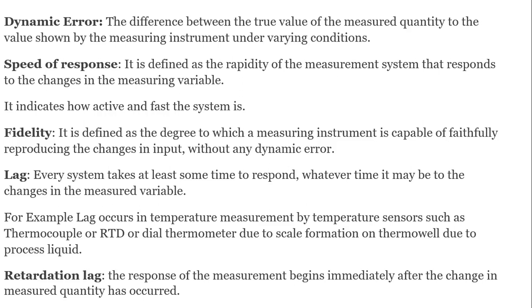Every system takes at least some time to respond — whatever the time lag may be — to changes in the measured variable. For example, lag occurs in temperature measurement by temperature sensors such as thermocouple, RTD, or dial thermometer, due to scale formation on the thermowell or due to process liquid.